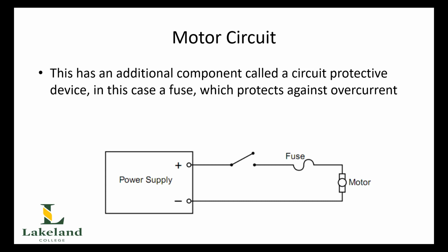Now, to give you a little bit of context for this, you may have had the experience in a machine shop or a room or an area that has a lot of electrical equipment in, that when you come in the morning and all the lights are on, and then you go around and turn on all the electrical equipment, the lights dim for a brief second, then they come back up. That is referred to as an overcurrent because the machines are drawing that much current when you turn them all on, and that's what caused the lights to dim.